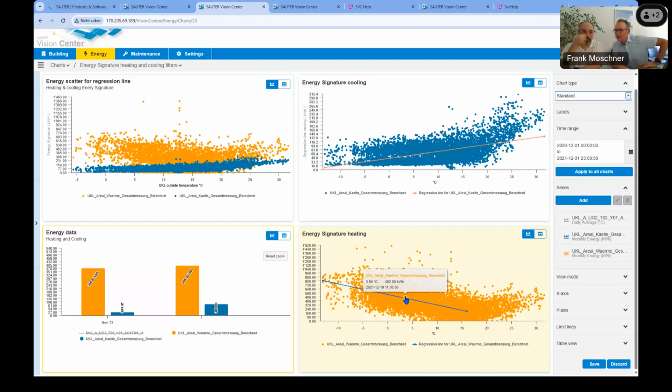One project with BACnet SC with any number of points possible. Yeah, that was a little change I have not mentioned in those slides. We started with 500 objects, and that was just as a teaser, maybe for energy, in 2019, 2020. Now with BACnet SC, within a project, we do not have a real limitation. Therefore, I mentioned here 20,000. Currently, we have projects in a range of 12 to 13,000. What you have seen, 20,000 is definitely reasonable.